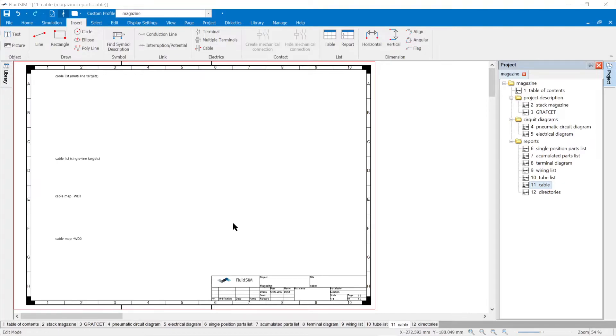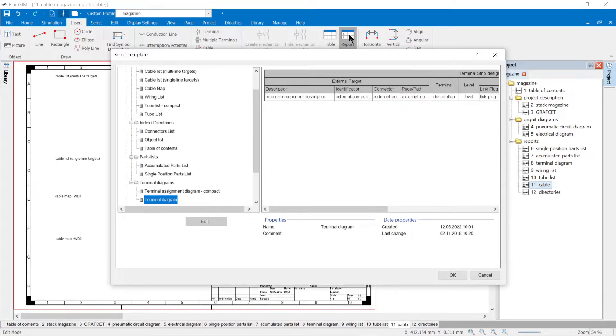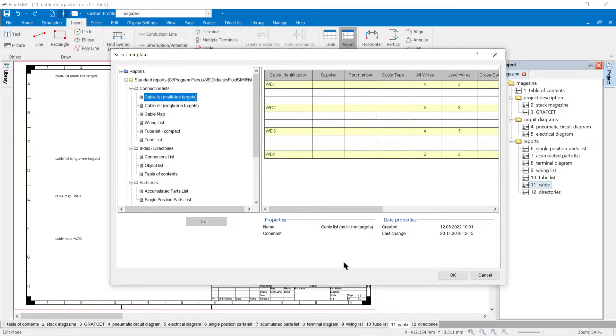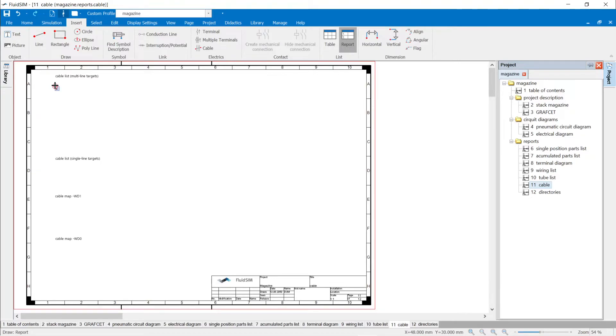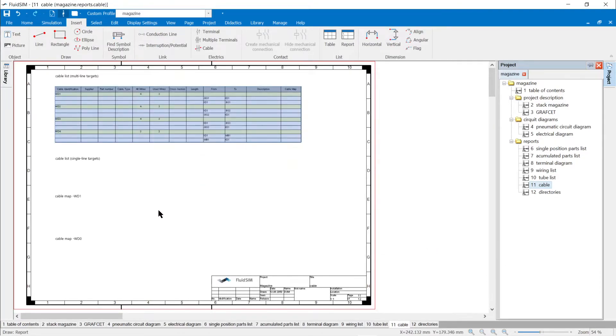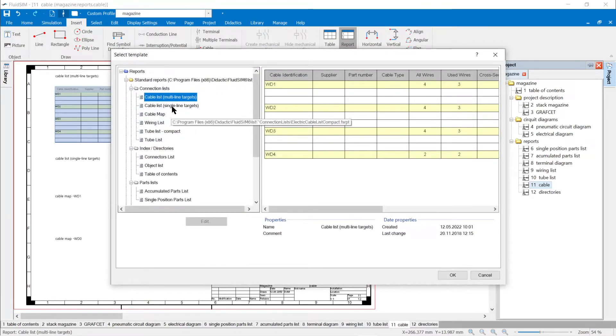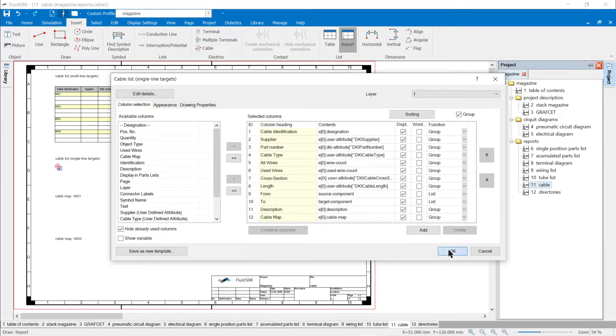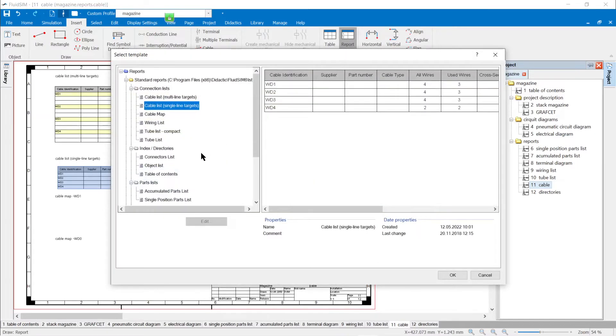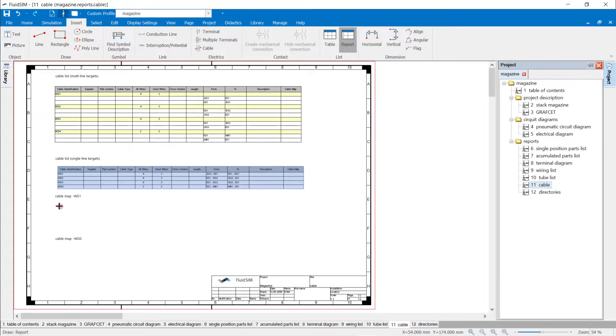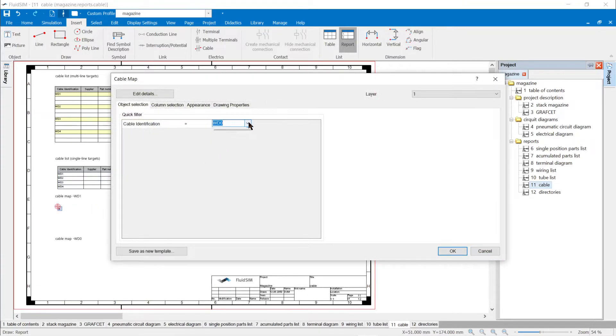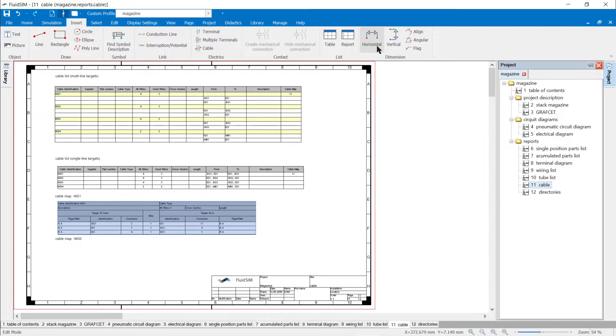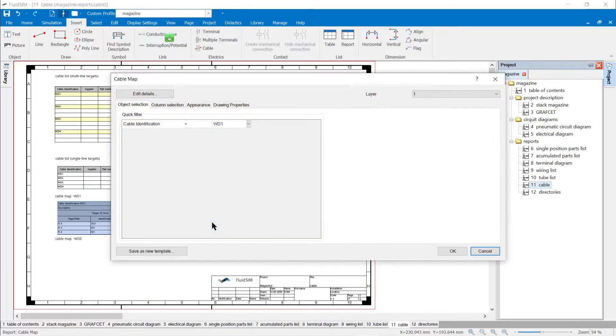Cable: The labeling of the cables in the electrical circuit diagram is also required in the various reports of the cables. The standard templates are cable lists with one or more lines, in which all cables of the project are listed. The multi-line cable list is first inserted here. For comparison, the compact form is inserted just below, listing each cable in just one line. A cable plan can be inserted for each cable. The desired cable must be selected in the properties dialog before it is inserted. The cable plan describes the start and destination of each core of the cable. The design can be changed at any time in the properties of the cable lists and also saved as a new template.